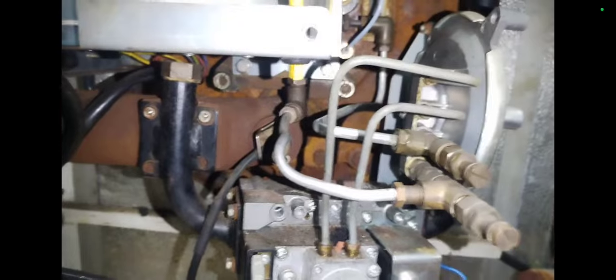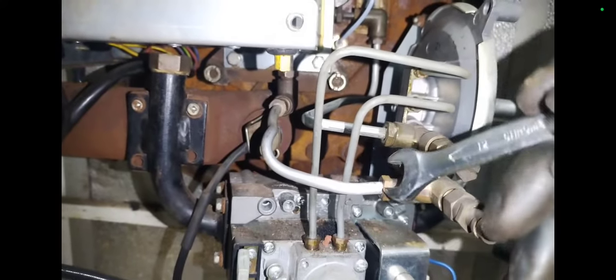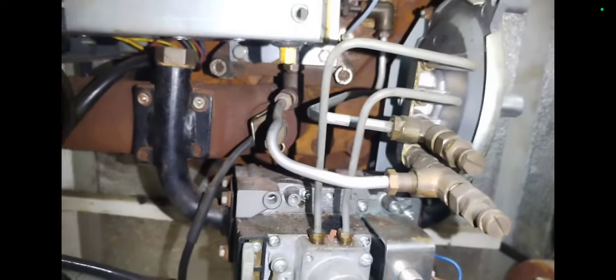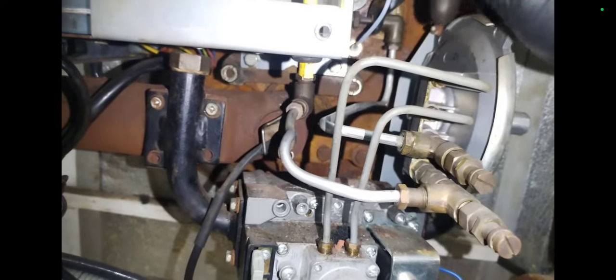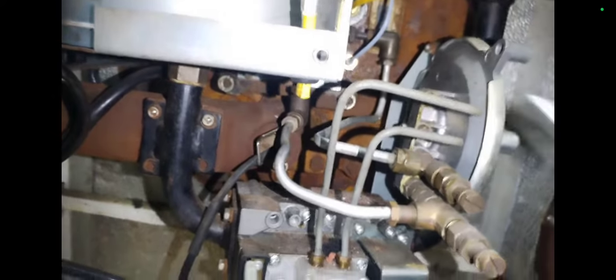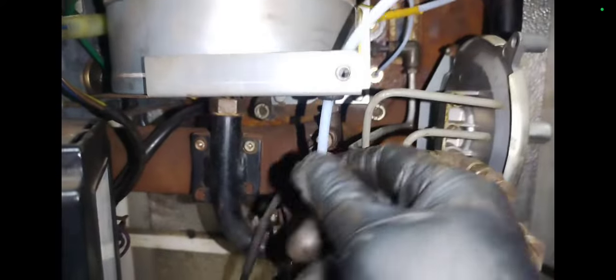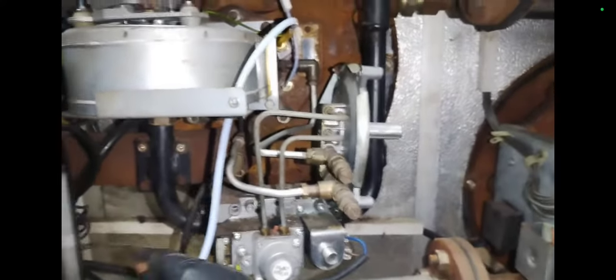It looks as though I was tightening up on this in order to test it, like I'd finished inspecting it. So I was just trying to nip everything up to make sure all was well on the unit. Remember to pop your ignition lead through here, it can be easy to forget. Your gas valve down there, your ignition board on the left, and your detection lead here. So it's all back together, but I believe this particular unit gave me some trouble in lighting.